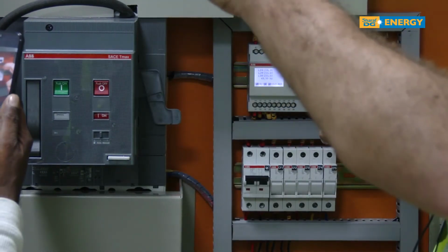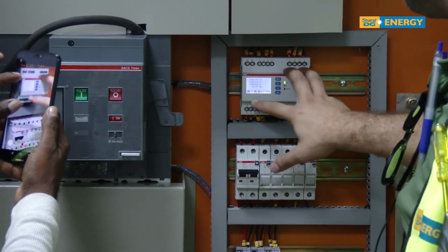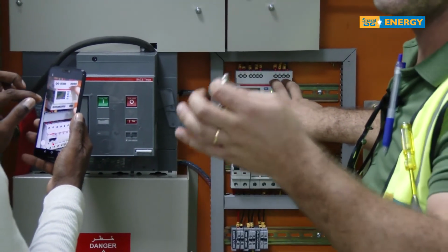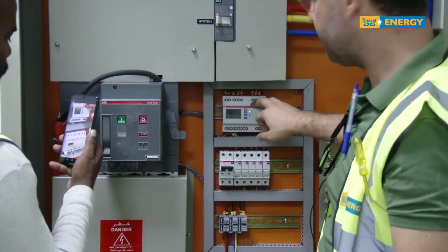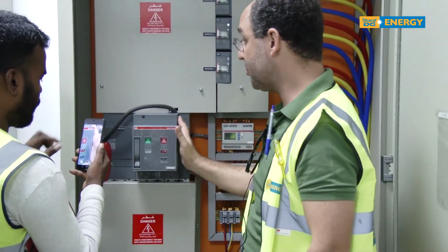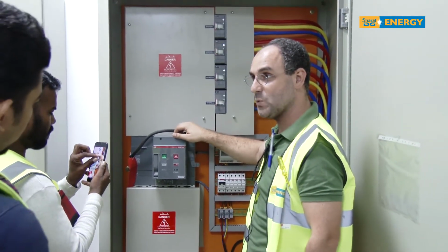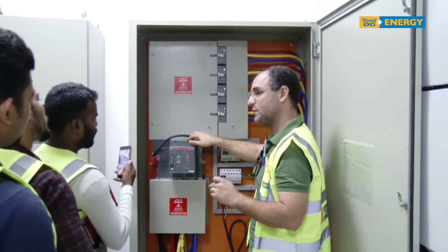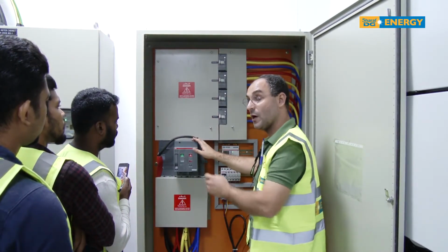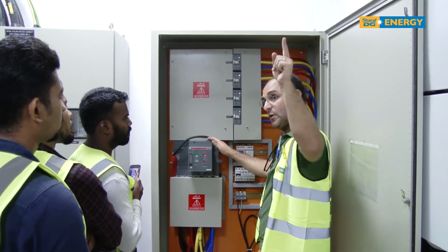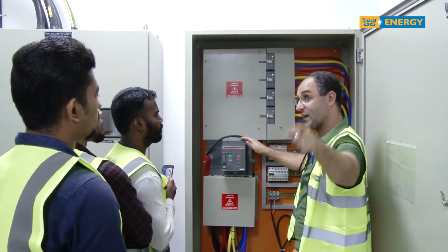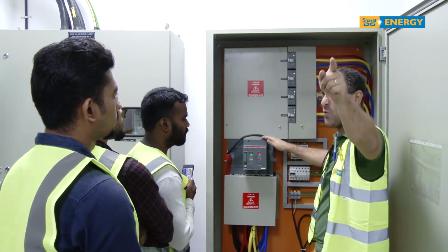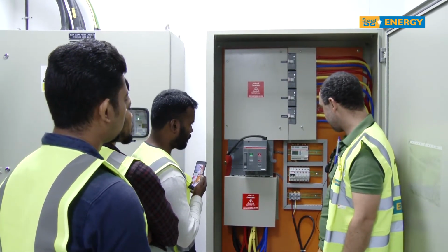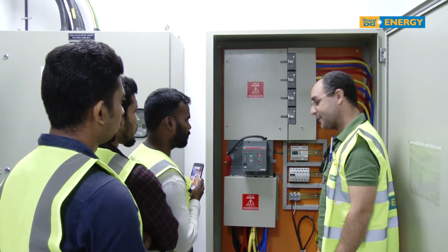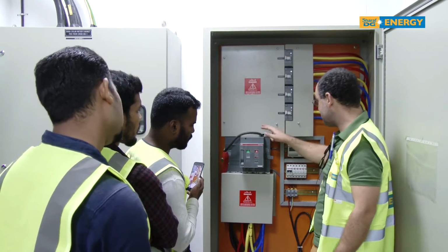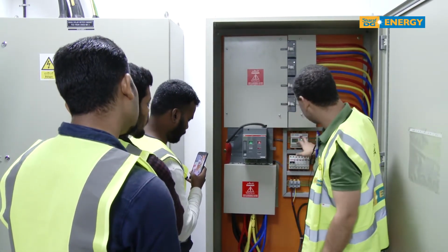Imagine now one inverter goes crazy. And instead of 49.99, starts making 55. This machine will know it. The relay one will send an order to trip this one until the conditions are restored. Okay? And if that is not acknowledged, then we'll send a second order to the secondary breaker here in the SMDBWH1. Okay? Are you with me, guys? The signal to the other one comes from here. The signal to this one comes from here directly.